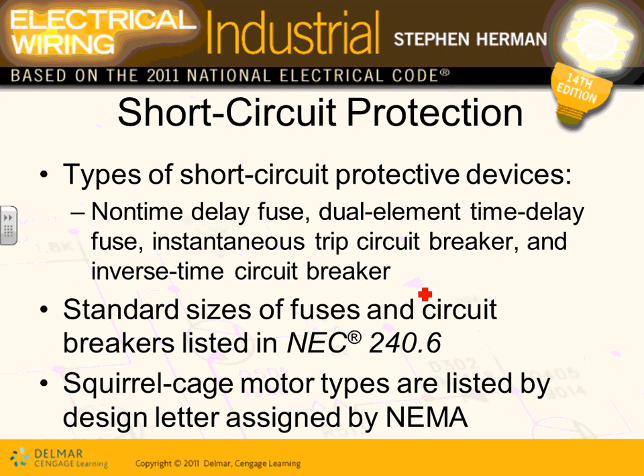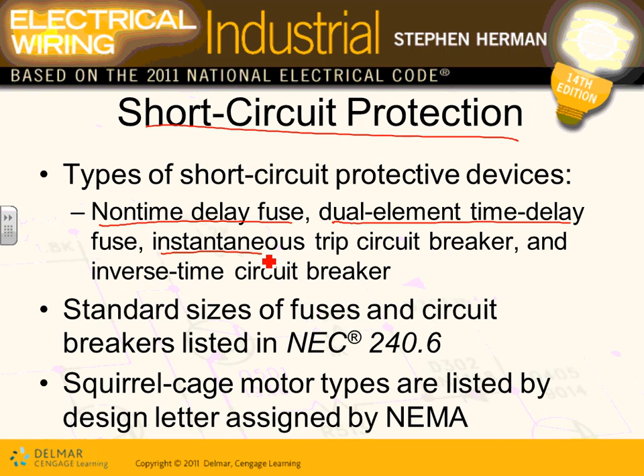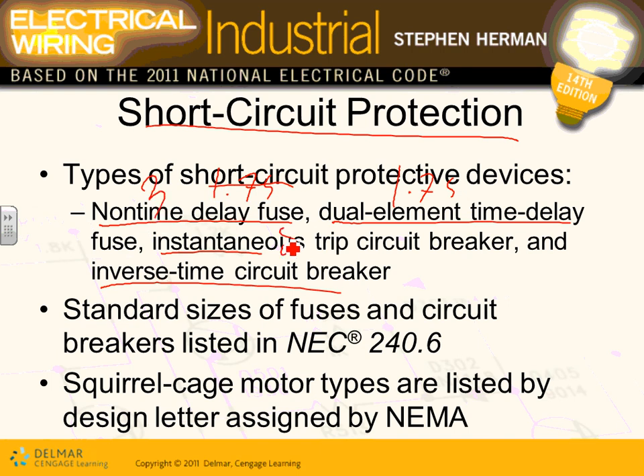For short circuit protection, you have different types: non-time delay fuse with a 3x multiplier, dual element time delay fuse at 1.75x, instantaneous trip at 8x, and inverse time type at 2.5x. The multiplier you apply depends on the type of protective device used.